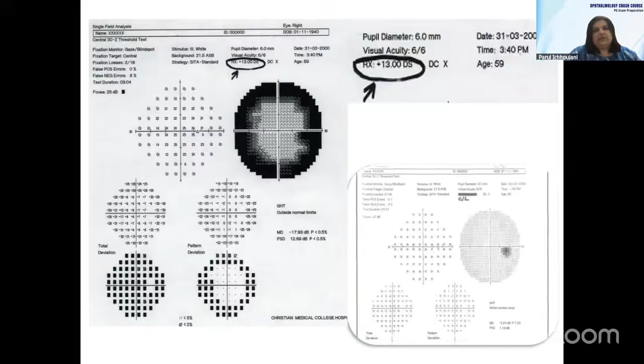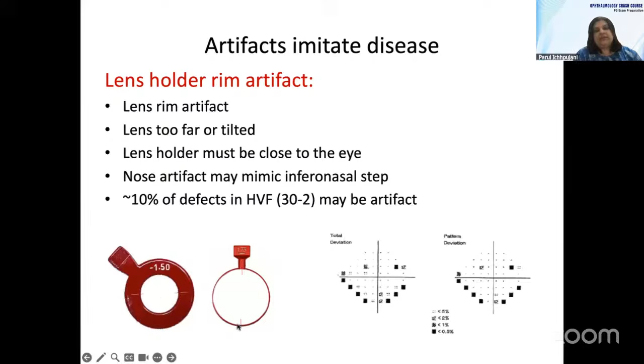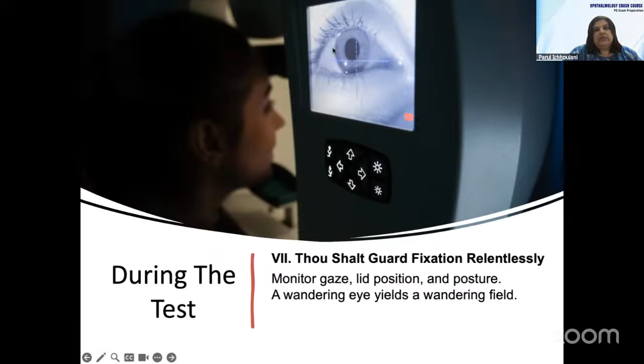Artifacts at times imitate disease. If there is a lens holder rim artifact, that means the lens is either not kept straight in its socket, or there is a nose almost touching the lens, then that nose artifact can cause an inferior nasal step. Almost 10% of defects in perimetry are artifact induced. Always remember, with most modern machines we get a set of thin lenses. If you're not able to find a lens, please don't substitute it with a trial frame lens. All these thin rim lenses are the ones that we have to use for perimetry. During the test, the technician should monitor the gaze, the lid position, and the posture. A wandering eye yields a wandering field. Most machines have a small window wherein you can see whether the patient has a wandering eye or not.